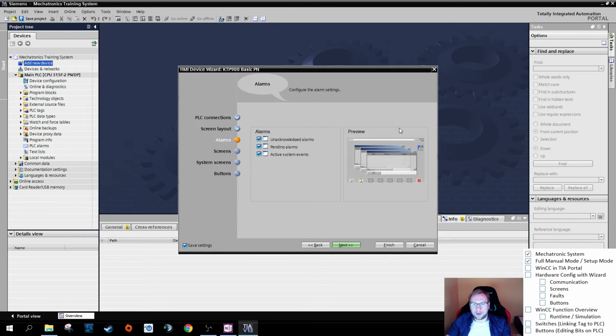So alarms. Alarms are, for example, if your PLC and your HMI are communicating, right? If the PLC cable, the Profinet cable, is disconnected from the HMI, the HMI is going to realize that. It's going to realize that I lost my brain. Well, how do you realize you lost your brain? But still, it's going to say, I lost my brain. The HMI knows, and through one of those alarms, it's going to tell you, my brain is gone. I do not have a connection to the PLC anymore. That's why those alarms are pretty important.